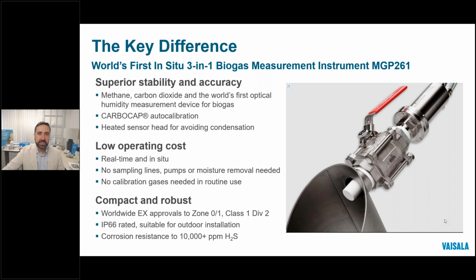Besides being the only in-situ moisture measurement for saturated biogas that is hydrogen sulfide compatible, we've also made sure that it's safe to use in EX-rated environments without having to resort to minimum distances from the process or remote enclosures. The 1.5-inch NPT threaded probe body installs directly into the pipe or through a 2-inch ball valve and has the electronics sealed and isolated from the process. With no moving parts or consumables, the IP66 rated probes are designed to be installed outdoors and in a variety of locations. We do not have a real maximum pipe diameter spec, but in situ installations could be done in as small as a 2-inch pipe with the right standoffs.